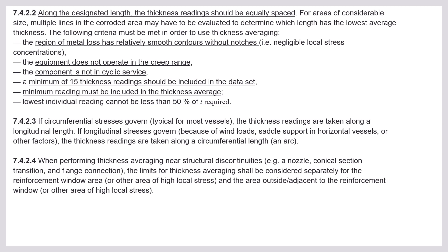To determine which length has the lowest average thickness, the following criteria must be met to use thickness averaging: the region of metal loss has a relatively smooth contour without notches; the equipment does not operate in the creep range; the component is not in cyclic service; and a minimum of 15 thickness readings should be included in the data set.